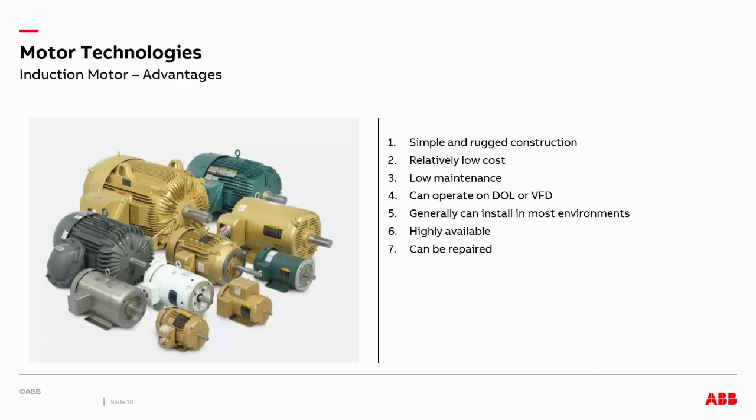And they can be serviced. We have motor shops that can service these. Some customers can even maintain their own motors, replace bearings if needed, or rewind motor windings if they short out. So as you can see, there are way more advantages of using an induction motor than there are concerns. So this technology has been around since the 1880s, and there's been considerable work done to improve performance and energy usage. The induction motor will continue to be the workhorse in all our industries for years to come.